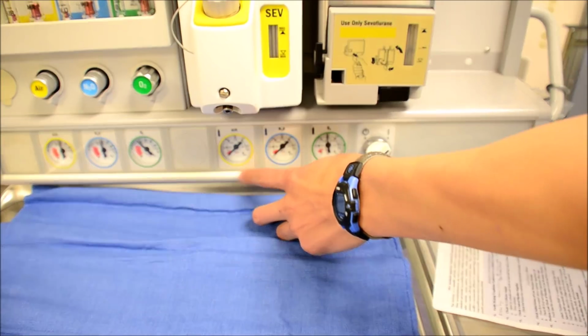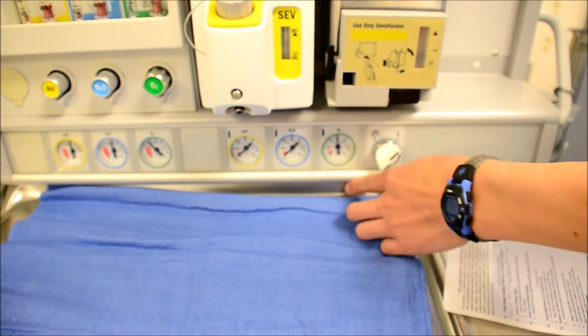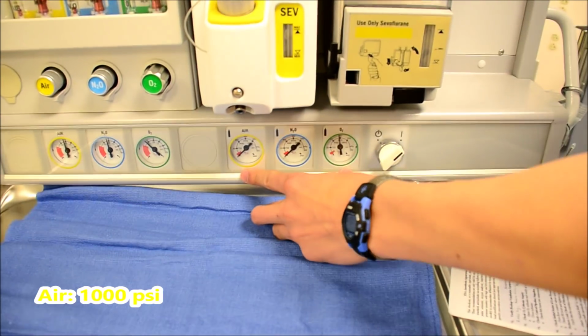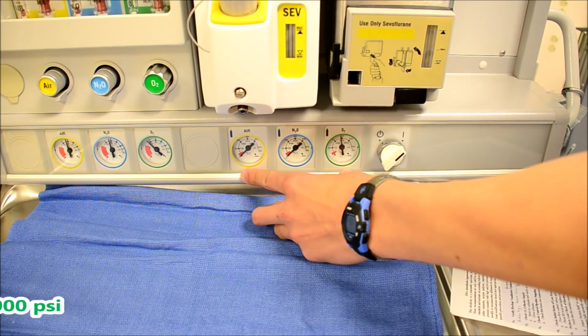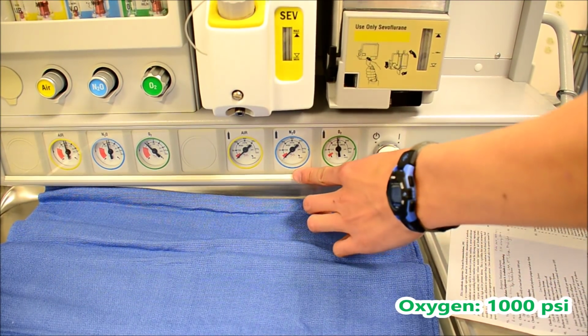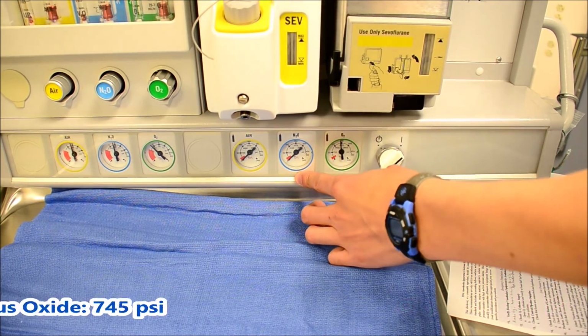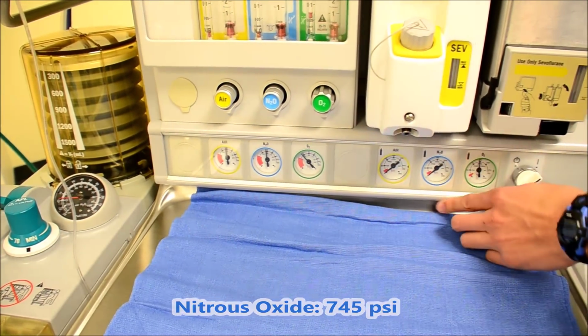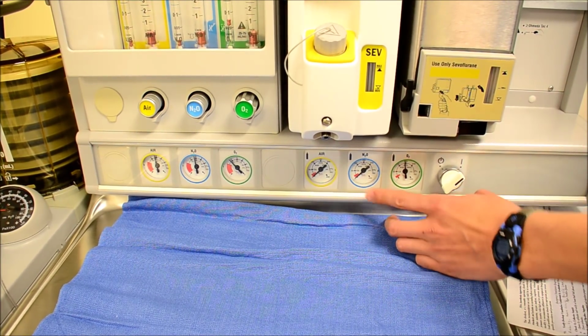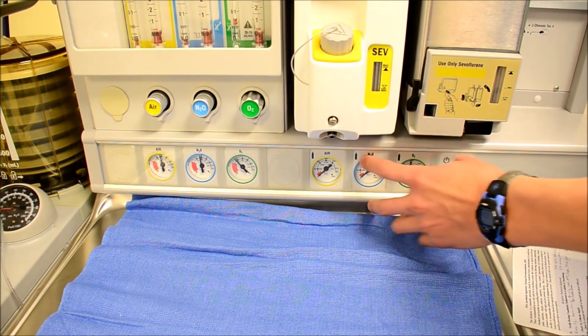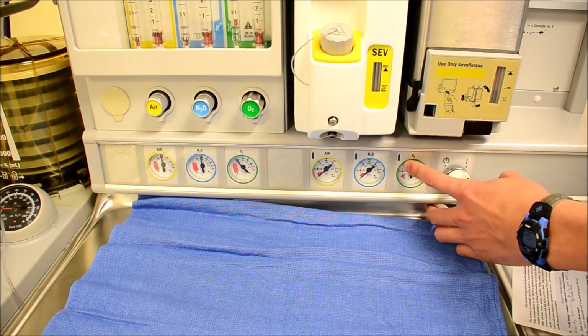So like I said, we have air, nitrous, and O2. Your air and your oxygen should have a pressure of at least 1,000 and your nitrous oxide of at least 745. You can tell the difference between your mainline supply of gas versus your pipeline or your cylinder, because there's a little cylinder picture with each one of these items.